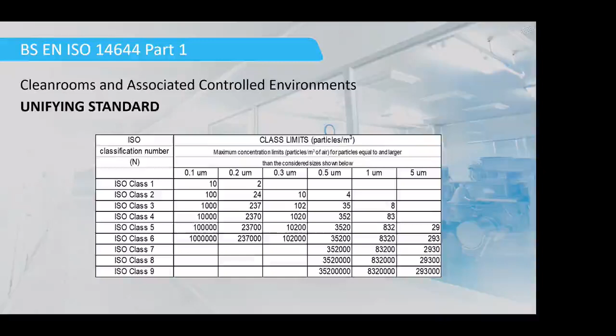Now the classification went through a change. It initially started out by counting the number of particles per cubic foot of air, and then it was a nice straightforward system. 1 particle per cubic foot was class 1, 100 particles was class 100. Then we went metric, so the whole thing became a lot less intuitive. What we do is multiply by 35.2 for any result, and that extrapolates out to a cubic metre. So the reason you've got these odd sounding numbers, 3,520 for example, is because we've done the conversion from imperial to metric.